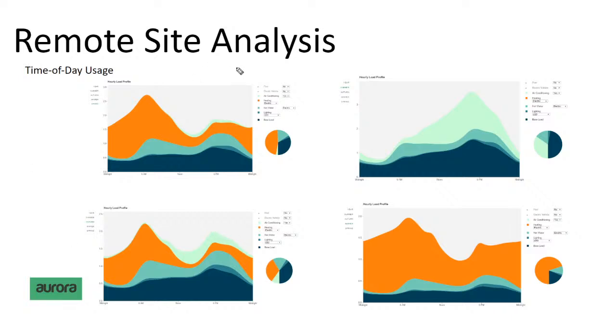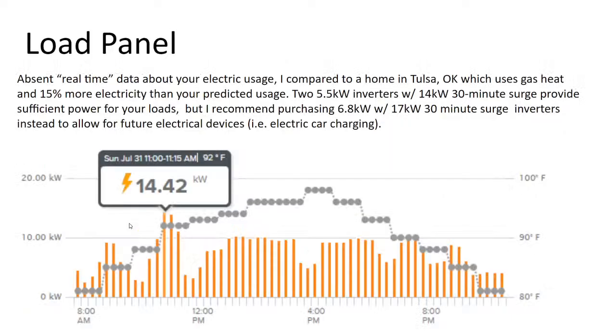The other way is to just make assumptions, maybe saying my peak load is going to be 2 or 3 times larger than my base load. What graphs like these load profiles do is smooth out the actual load. The actual load is spiky, dropping and then spiking up, dropping and spiking up again. So your actual load power output requirements could be very different than what smooth interval data delivers. Even 15-minute by 15-minute interval data can't tell the whole story. Your utility will often provide this 15-minute interval data, but you can assume the highest 5-minute load is going to be taller than the highest 15-minute load.